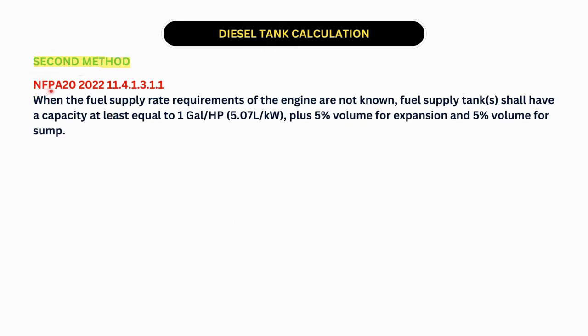I will now read what NFPA 20 states about the second method. As per edition 2022, when the fuel supply rate requirements of the engine are not known — meaning fuel consumption is not known — the fuel supply tank shall have a capacity of at least 1 gallon per HP, plus 5% volume for expansion and 5% volume for sump.